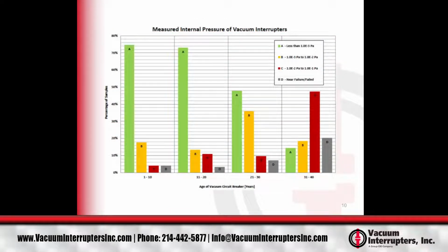Several years ago, we tested a group of vacuum interrupter breakers in Gainesville at our CBS shop. We had over 300 of one type of circuit breaker that they manufactured over a 40-year period. So we took those vacuum circuit breakers and MAC tested every single VI on all the breakers. What you see here is a plot of all of the results with the different levels of pressure: green being good, yellow being mid-range, red being near failure, and gray failing our test.